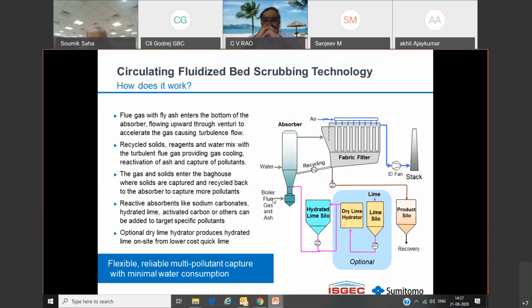The idea of doing this is that we want to utilize unused lime in this circuit, which would otherwise pass through the system. So this circulation system is basically to make it effective, to have more residence time for proper reaction and lesser wastage of reagent. Typically we use a reagent in this technology. It could be sodium bicarbonate, hydrated lime, or quick lime, which is converted to hydrated lime.